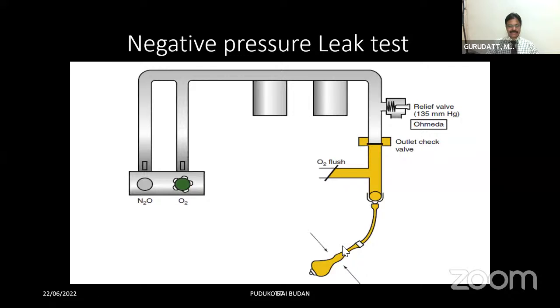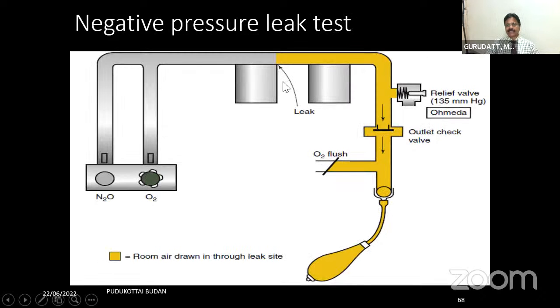In the negative pressure leak test, you have a bulb connected to the common gas outlet. You keep on squeezing it and drain out all the gases that are present inside. The bulb, which is collapsed, should remain collapsed for at least about 10 seconds. Then you know that it is leak proof. Because there is a check valve, you can open the vaporizers even after that. Because you are creating a negative pressure, this negative pressure leak test also checks for any leaks from the flow meter assembly to the common gas outlet. That is why the negative pressure leak test can be done for both GE machines and Draeger machines, and it is also called the universal leak test.